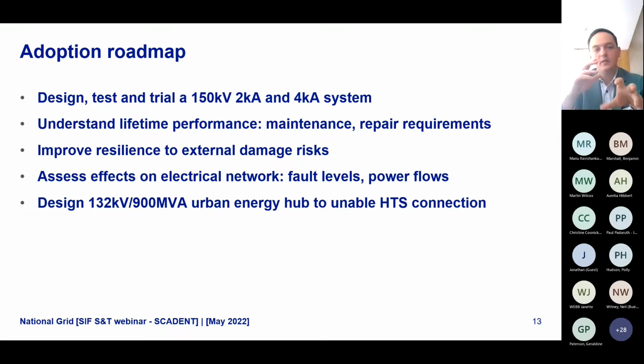And last but not least, which is often neglected, is what do we do with this amount of power at 132 kV inside a city? Because normally at 132 kV it's about 250 MVA substations. So that means we need to rethink how we design the substation to adopt this amount of power and distribute it around the network, working as a hub where all this power is delivered from the outside substations and then distributed in the city.